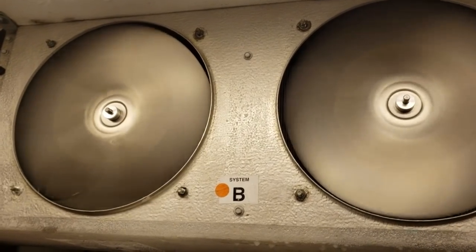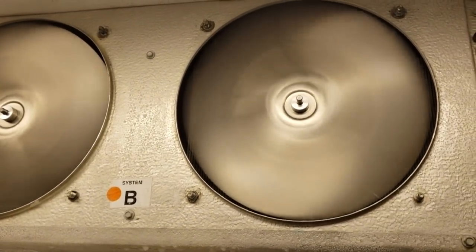The camera might not be able to see it, but this motor over here is spinning a lot faster than the other one — this motor is barely going at all. And it has 208 volts. So there's definitely something going on with that motor.